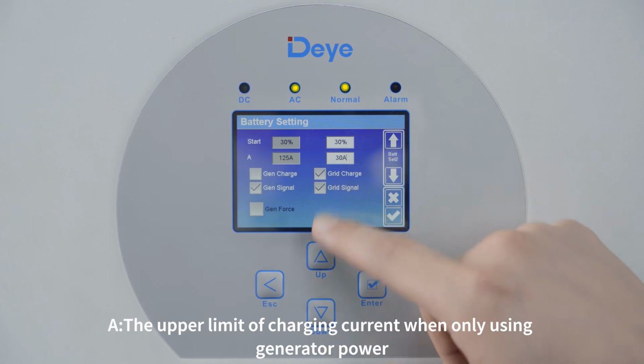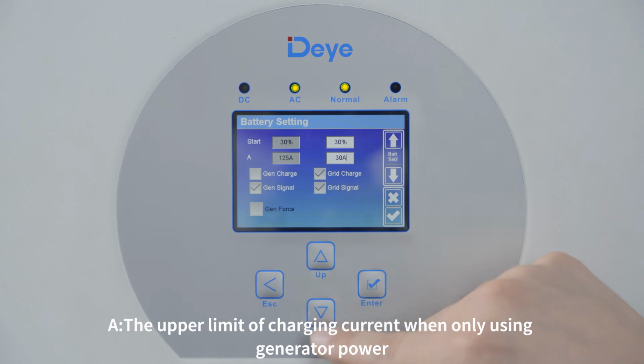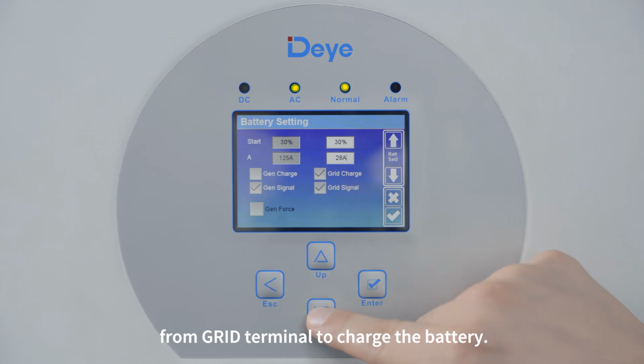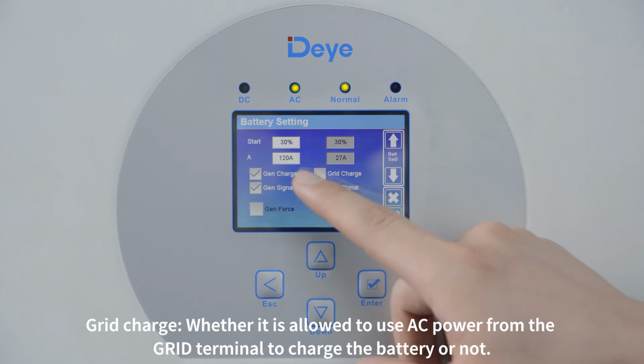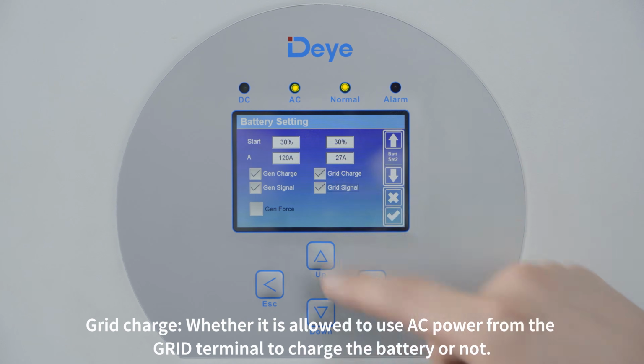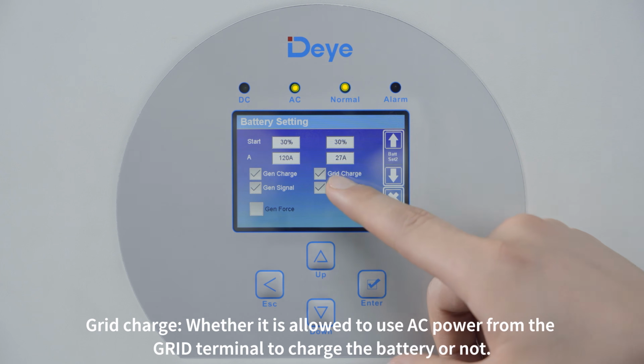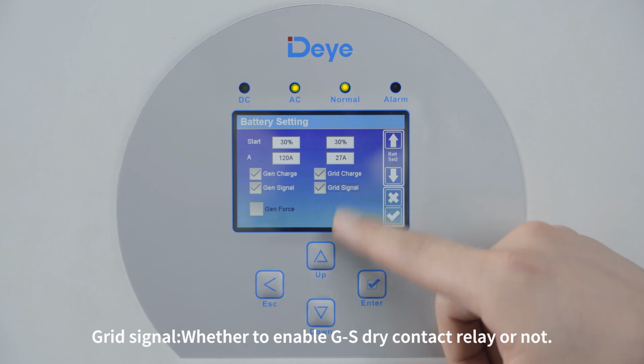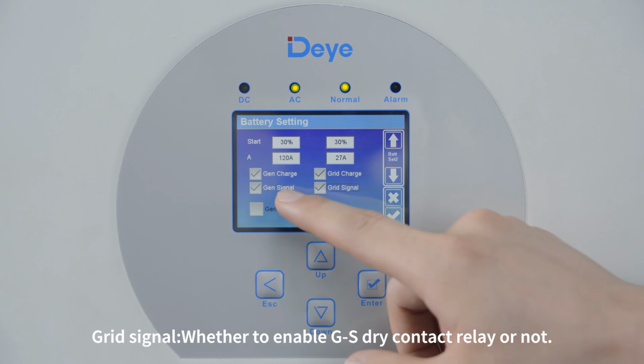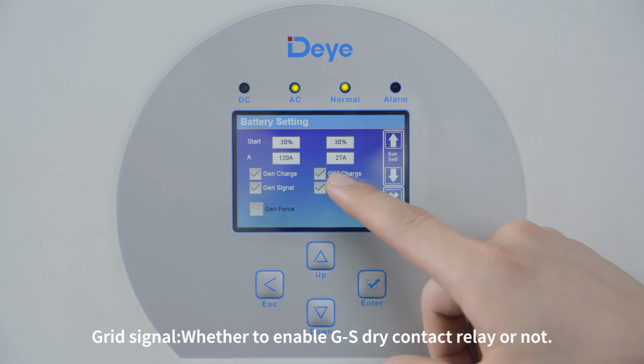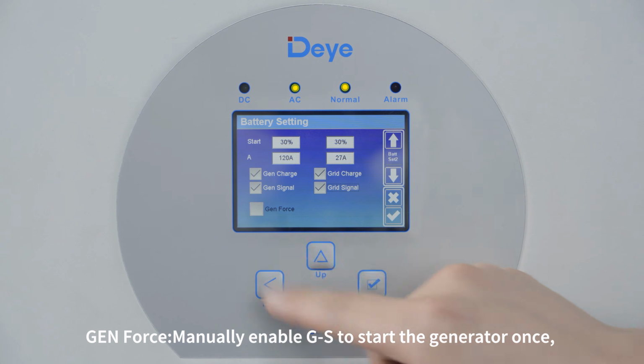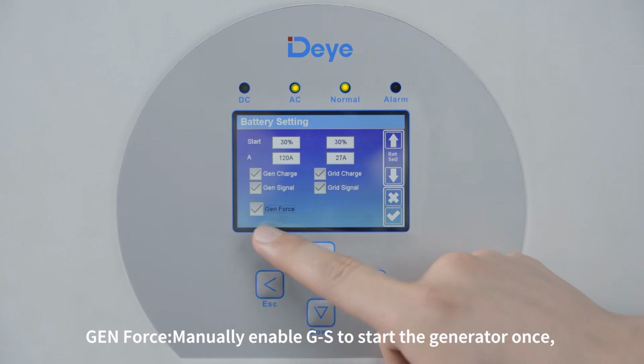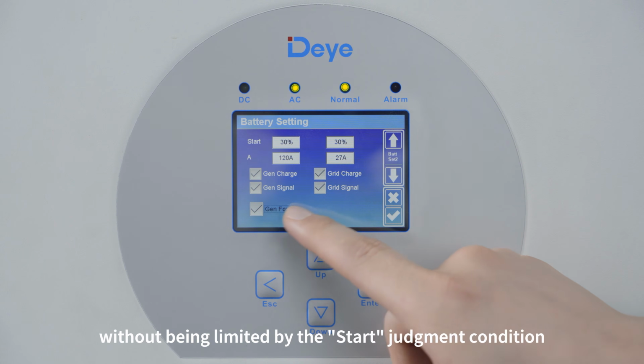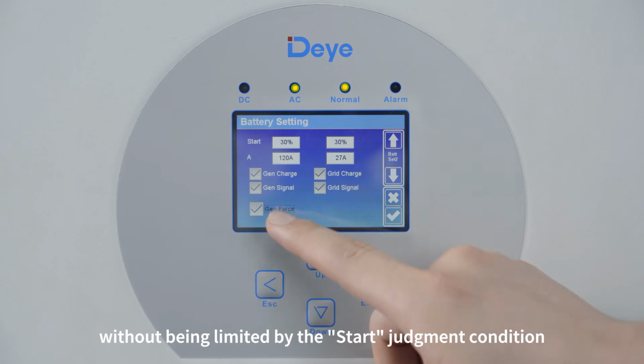8: the upper limit of charging current when only using generator power from the grid terminal to charge the battery. Grid charge: whether it is allowed to use AC power from the grid terminal to charge the battery or not. Grid signal: whether to enable the GS dry contact relay or not. GEN Force: manually enable GS to start the generator once, without being limited by the start judgment condition.